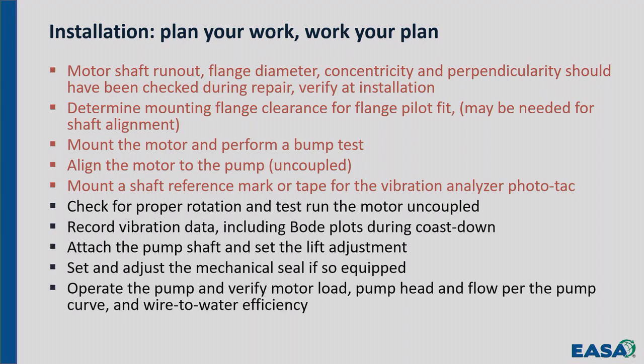Okay? Let's see. Check proper rotation. I'm going to show you some pictures on that. Before you couple it to the pump, you do not want to start a motor in reverse direction as coupled to the pump. I'll show you some pictures on that. So you're going to check rotation. You're going to start and run the motor. You might as well have that phototach on there before you do it. Then you record your vibration data, including Bode plots during the coast down.